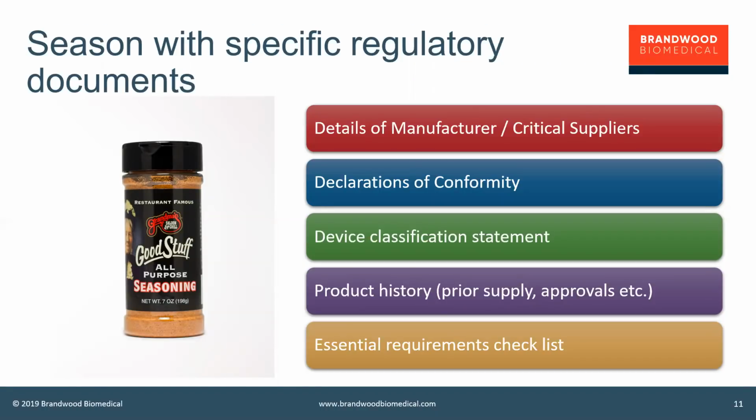Product history, as we have more and more products that are iterations of previous products on the market, it is absolutely critical for you to describe the product history. So if this is truly a new product that it's never been done by you and you've never had anything, you're not going to have a product history, and that's not the end of the world. But in the situation where you have a product on the market and this is what you term as an upgrade or an advancement in the technology, you want to be able to show the differences between those two devices and give that regulatory history for a regulator to look at.